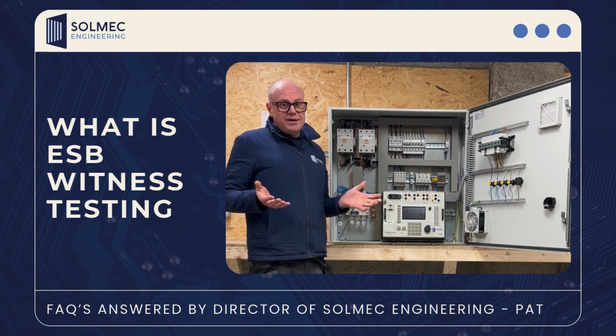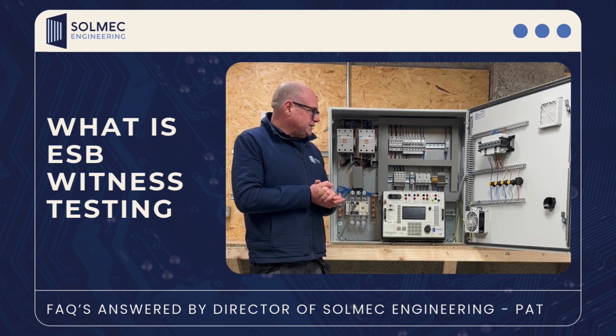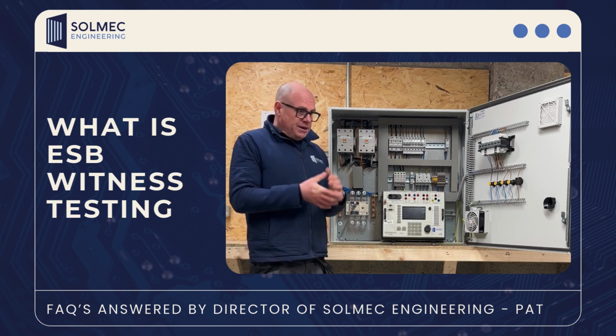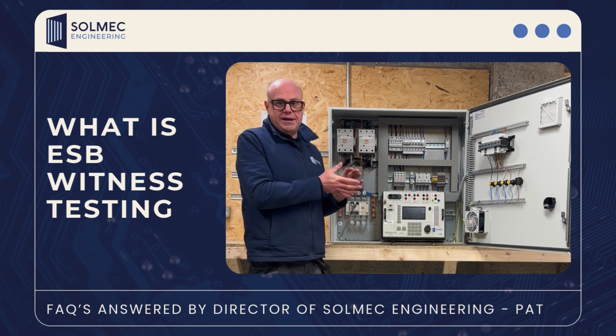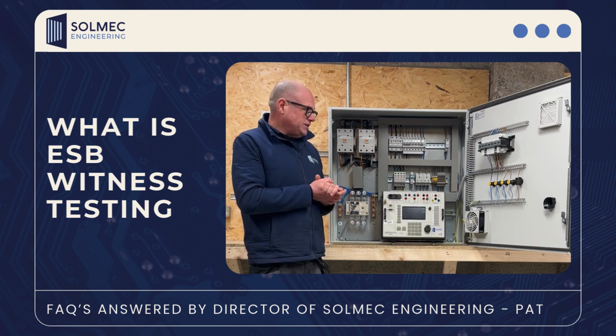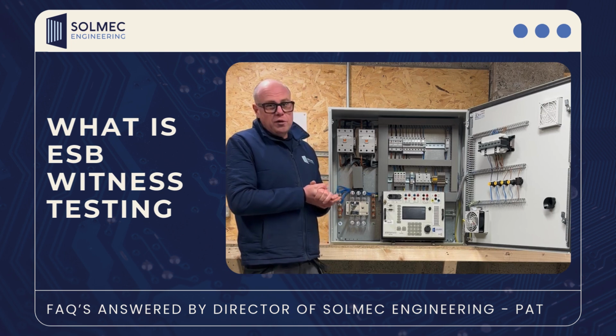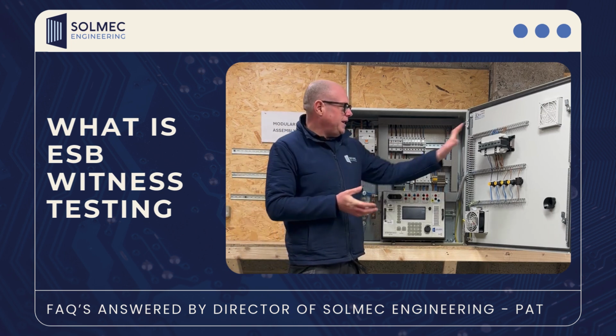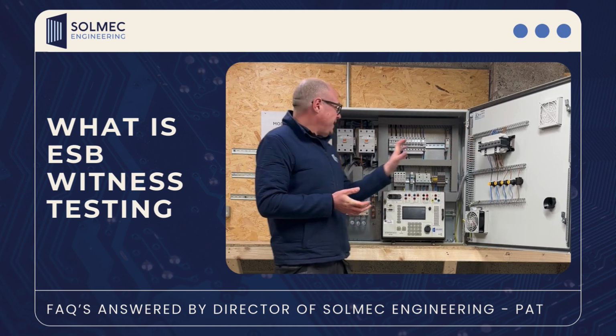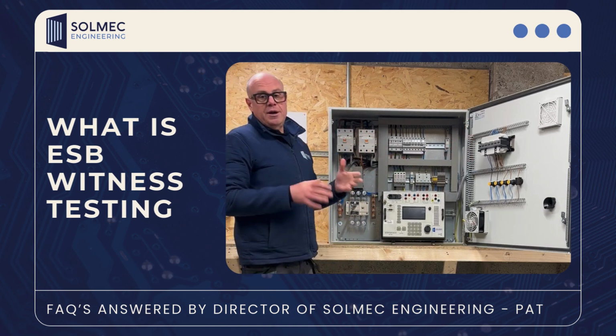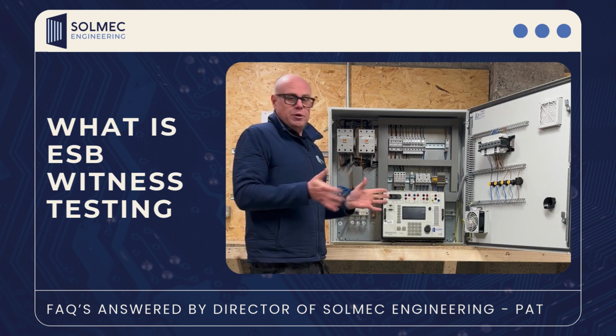So what's involved in it? Basically, a representative from the ESB, myself from Solmec Engineering, and you, the installer of the G10 and the PV solar system, will be on site and prove that under fault conditions the relay will do what it's supposed to do. Basically, cut out the contactor when there's a fault condition that will not be allowed out onto the grid.